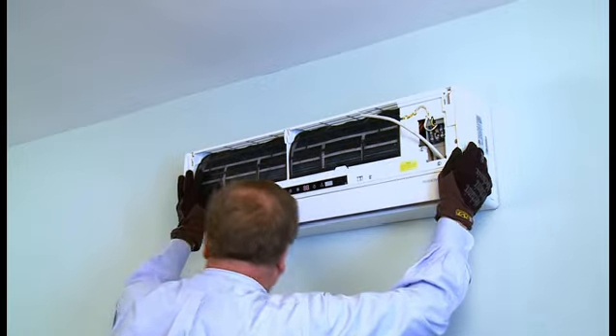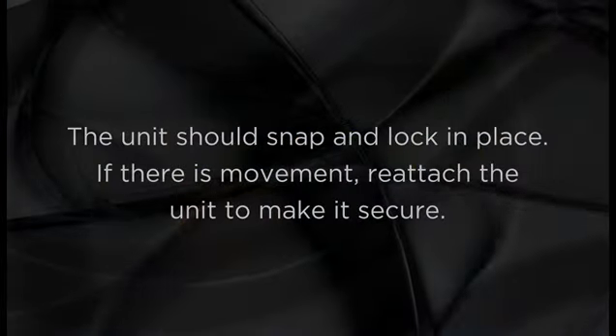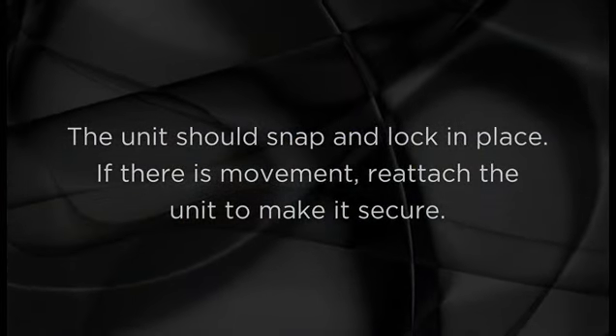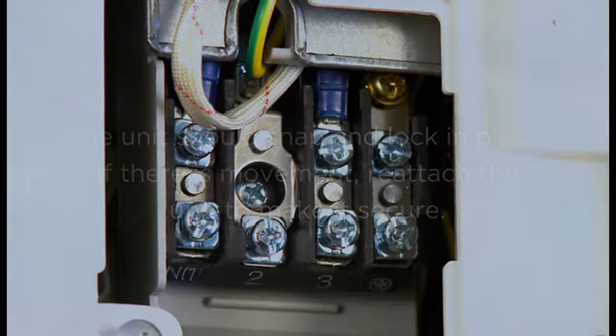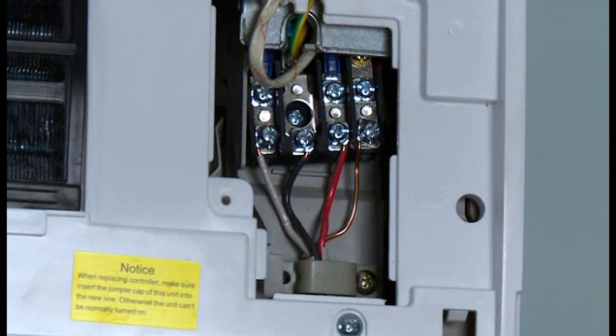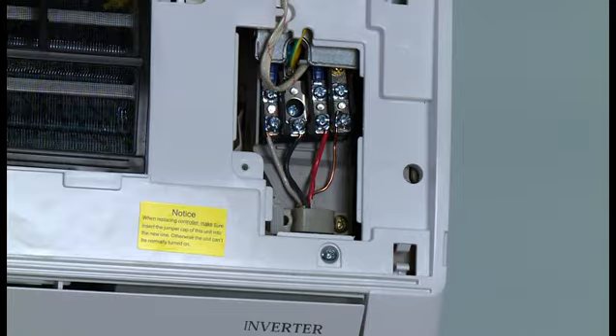The unit snaps and locks into place. If there's movement, the unit is not secure and needs to be reattached. Attach the control wire leads to the electrical box. Replace the electrical box cover. Tighten the screws. We will now install the exterior unit.